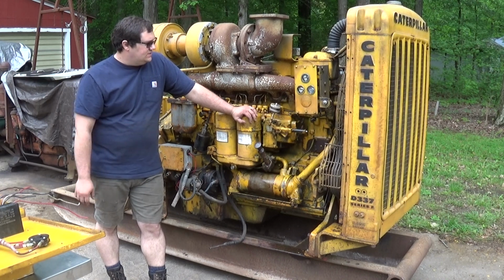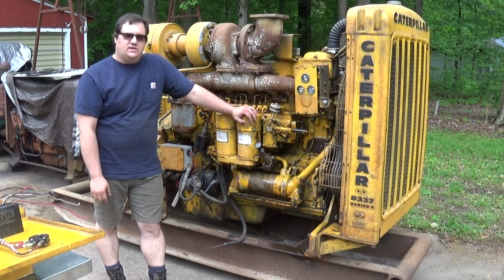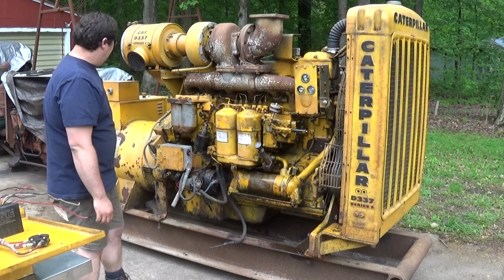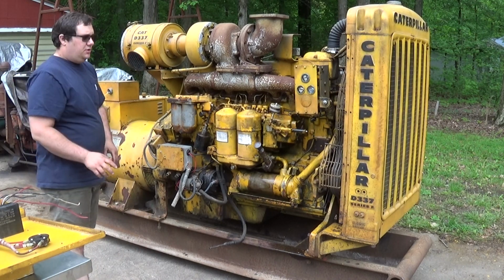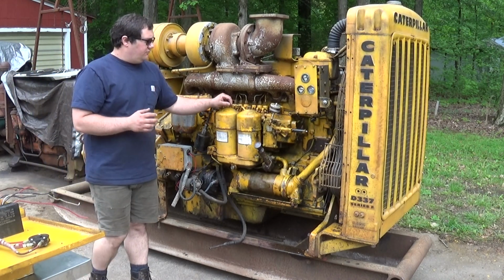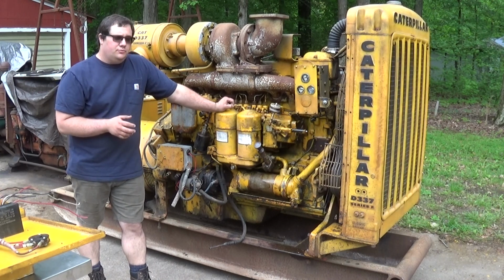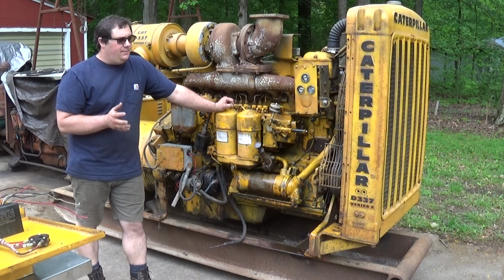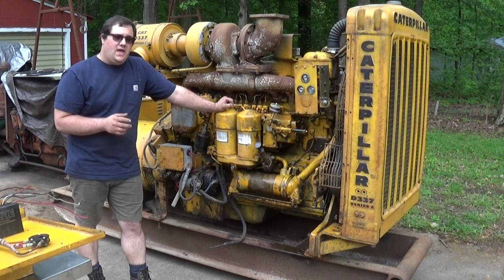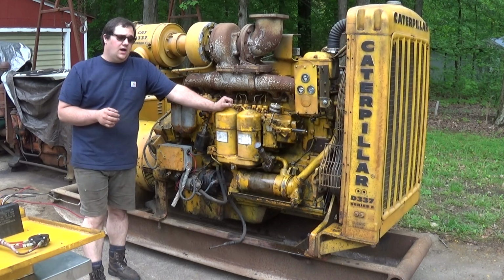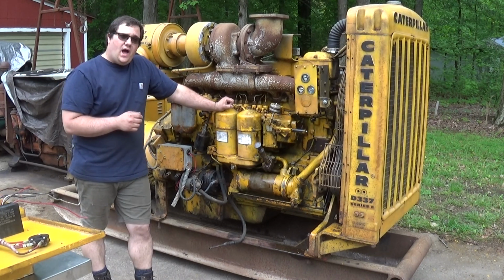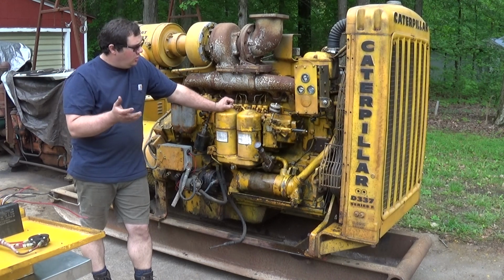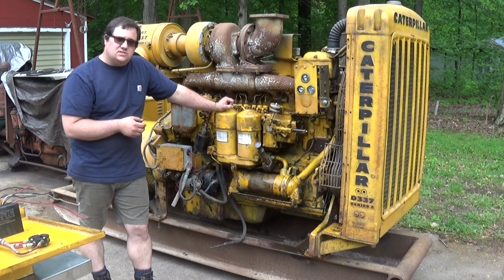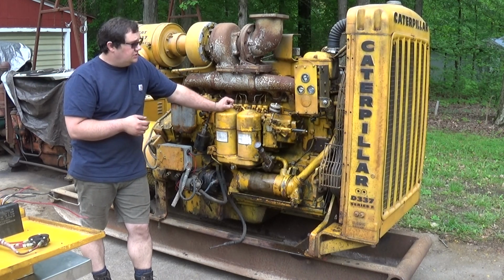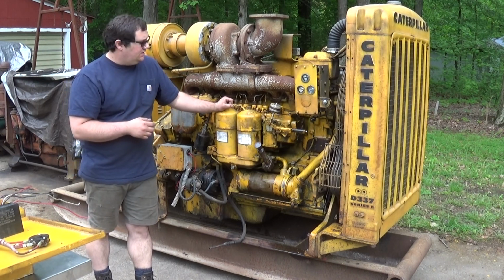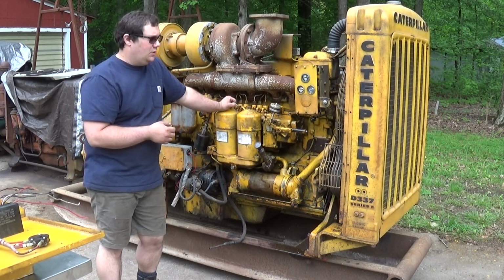I want to see if we can get this Cat D337F genset running. I don't have a lot of backstory on this unit, but I do know it was removed from a hospital on Long Island about 10 or 12 years ago, and it's been stored in a barn since that time. I don't know why it was taken out of service, or if there are any serious issues with it. I do know it turns over, which is good for things I seem to acquire.